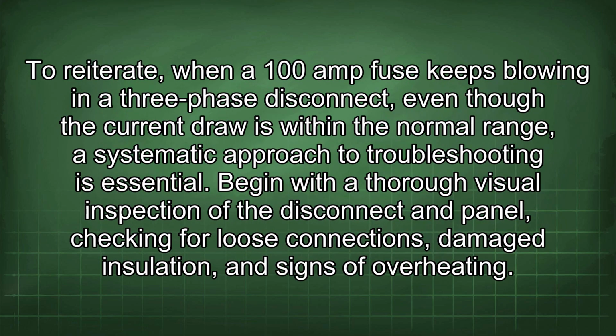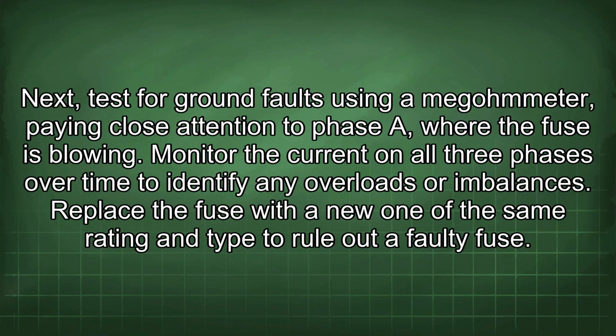To reiterate, when a 100 amp fuse keeps blowing in a 3-phase disconnect, even though the current draw is within the normal range, a systematic approach to troubleshooting is essential. Begin with a thorough visual inspection of the disconnect and panel, checking for loose connections, damaged insulation, and signs of overheating. Next, test for ground faults using a megohmmeter, paying close attention to phase A, where the fuse is blowing. Monitor the current on all three phases over time to identify any overloads or imbalances.